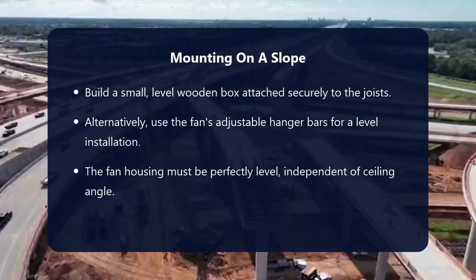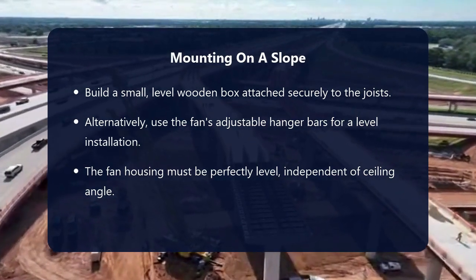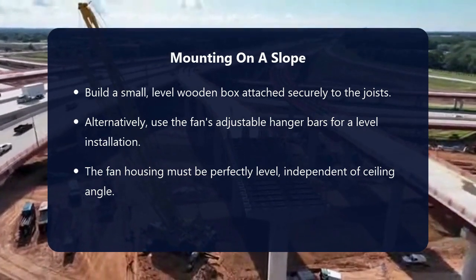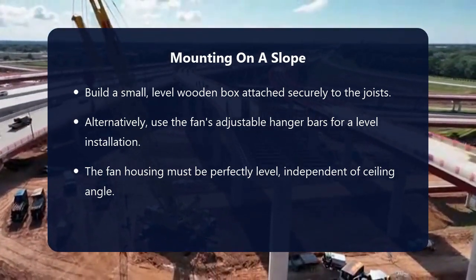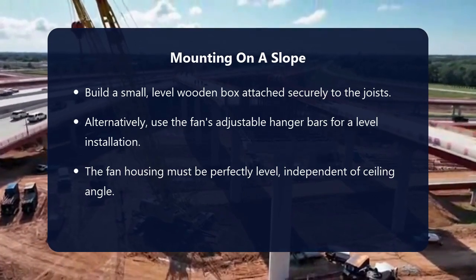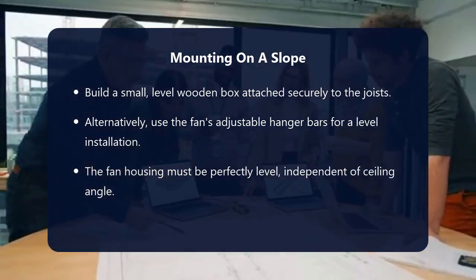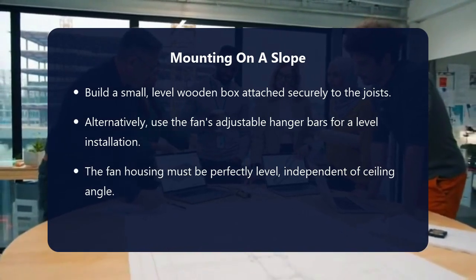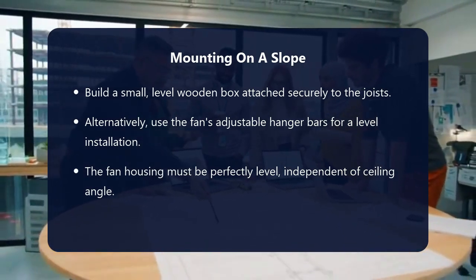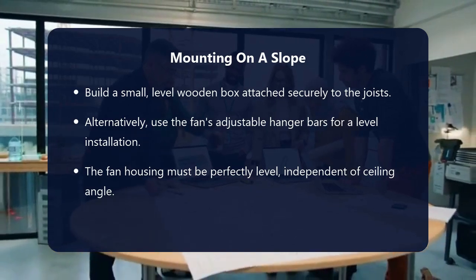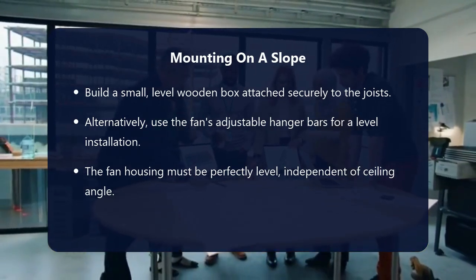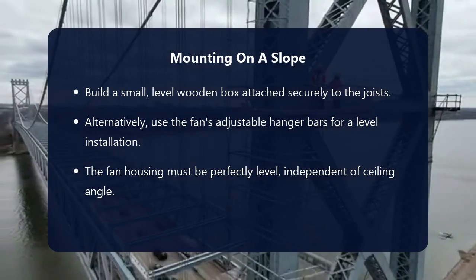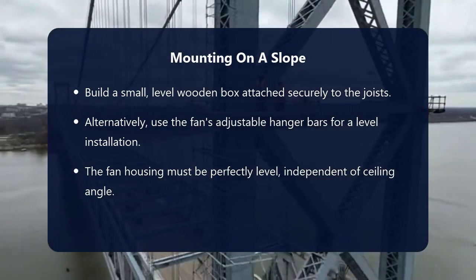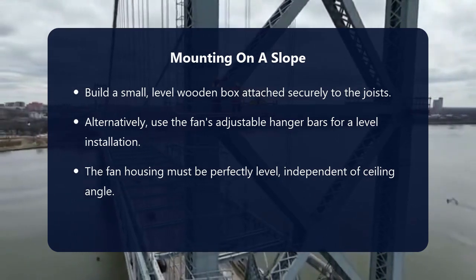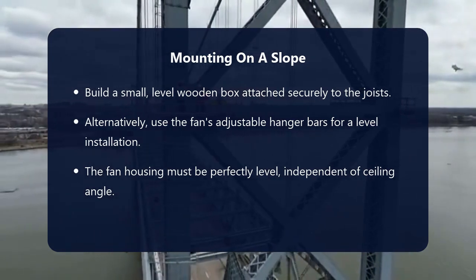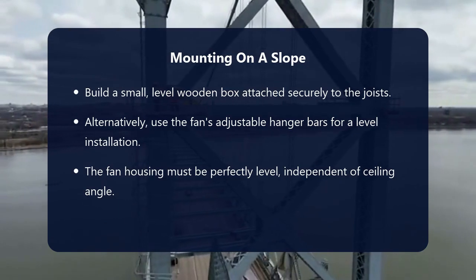Now for the most important part, mounting the housing. You have two primary methods to create a level mount on an angled surface. The first method is building a level box. You will construct a small, square frame out of 2x4 lumber. This box needs to fit snugly between the two ceiling joists. Attach the box to the joists, ensuring its bottom edges are perfectly level. You will then mount the fan housing directly to this level wooden box.